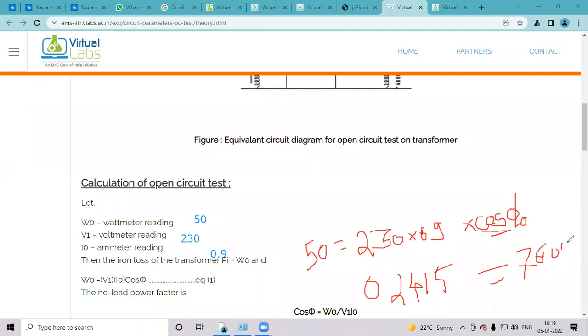While telling the no load condition of the transformer, I told one sentence: at no load condition, the no load current will not lag the voltage by exactly 90 degrees, but it is less than 90 degrees.